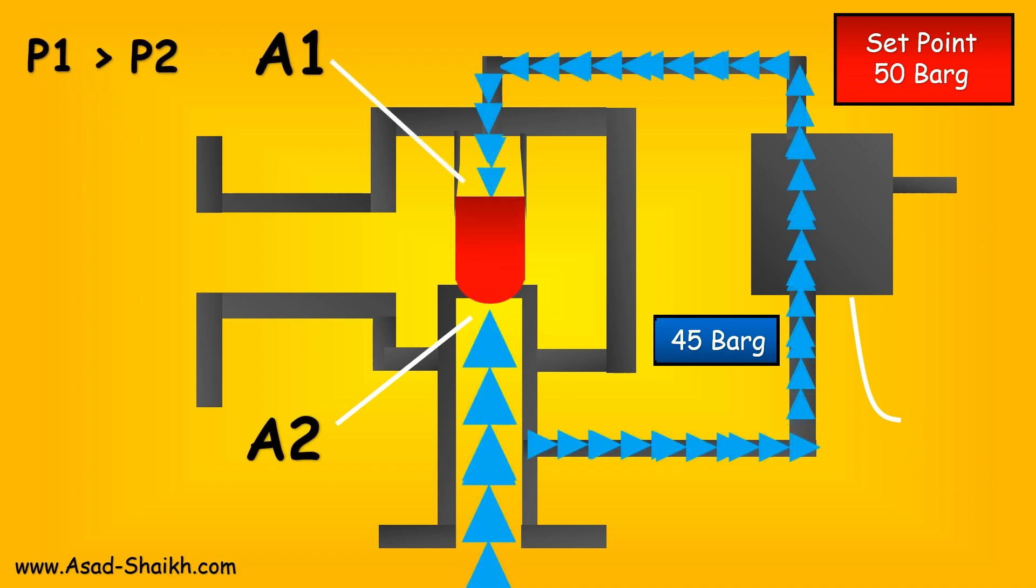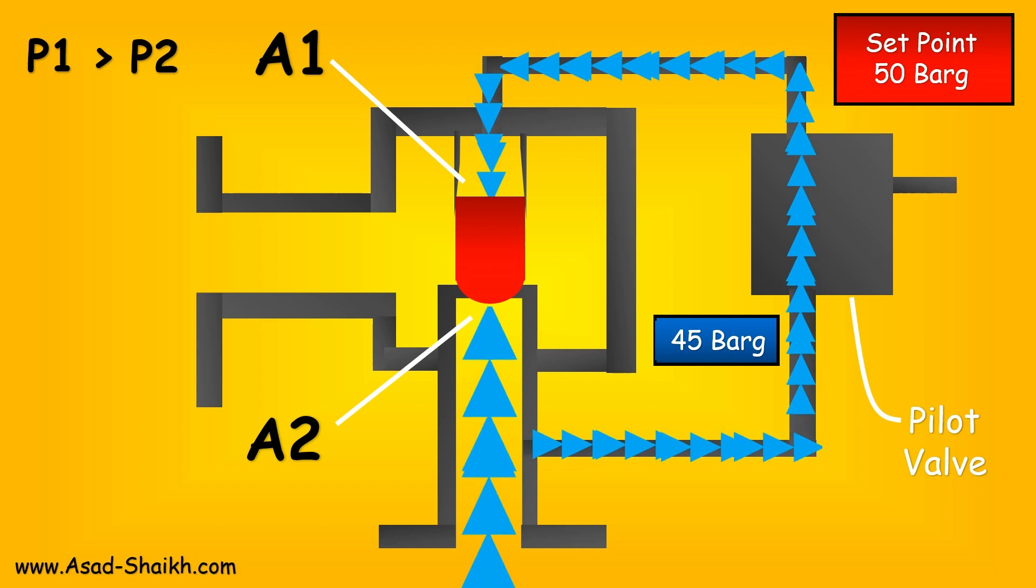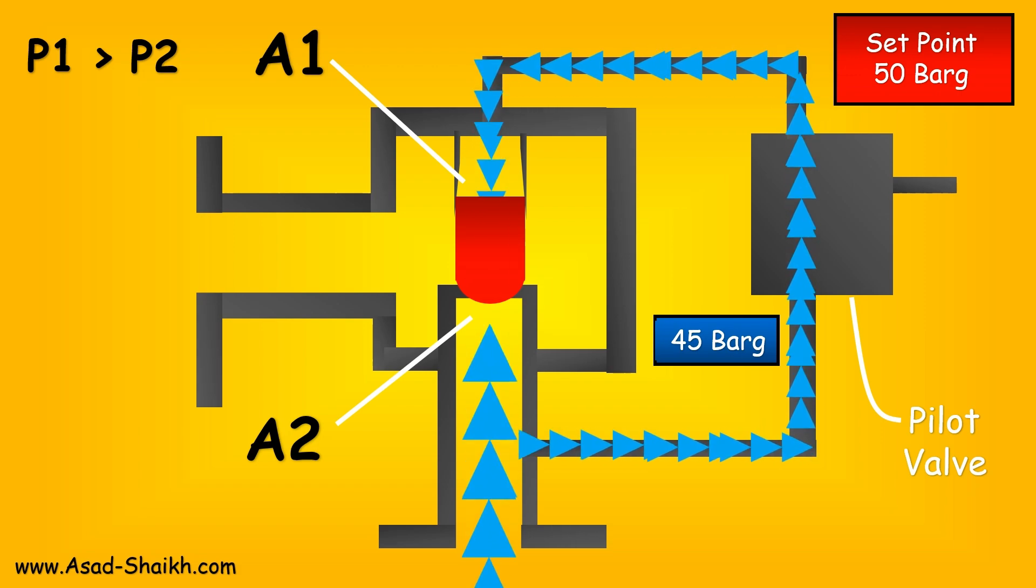This is going to allow the same pressure to go from the pilot to the inlet side. It is going to go to area A1, and if it goes to area A1, your pressure P1 is then going to be greater than your pressure P2. This is how your pilot relief valve gets back into its closed position again.